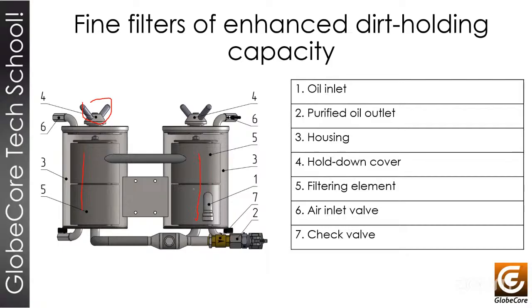And also we have the air inlet valve. When we are charging the oil for the first time in the machine, we recommend opening these valves to release the air inside these filters. When you see the oil coming out from these valves, the recommendation is to close them to avoid the oil continuing to get out, but you will have removed air from the filters, and that will allow you to have better filtration inside these filters.